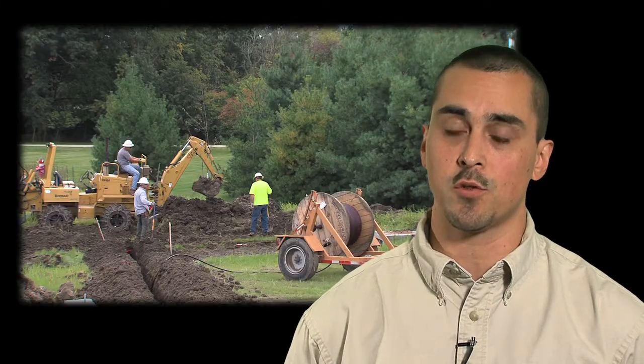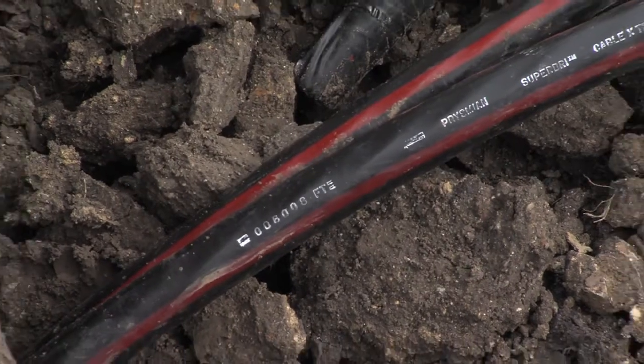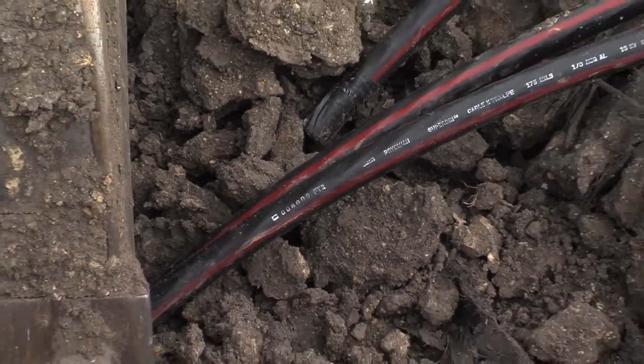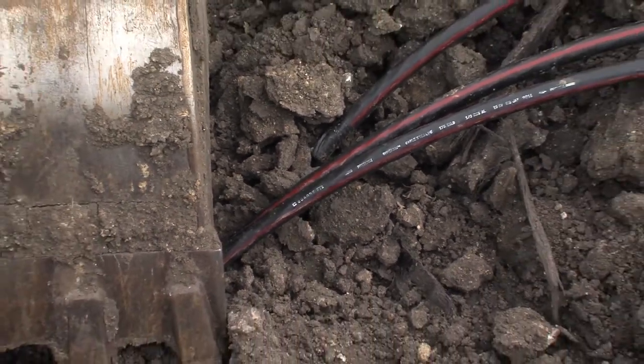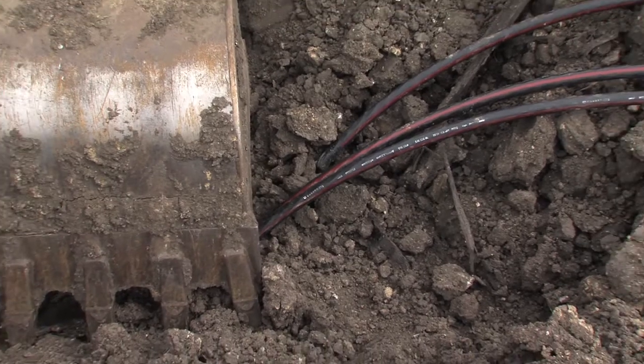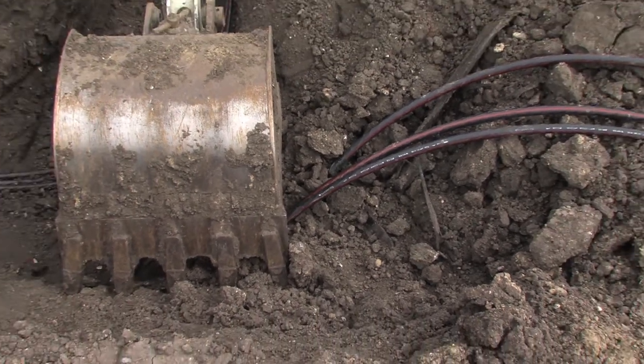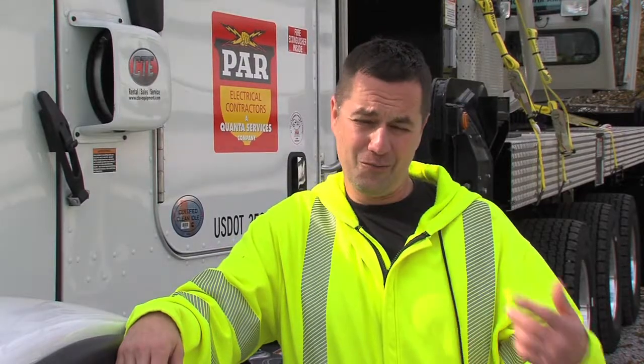If an excavator strikes a primary conductor, the system is designed to trip. However, the fault may actually be seen as load on the system. So what it does is it increases how much energy gets transported to that location. If you're running a trencher and you trench into an underground facility, your machine will become energized.